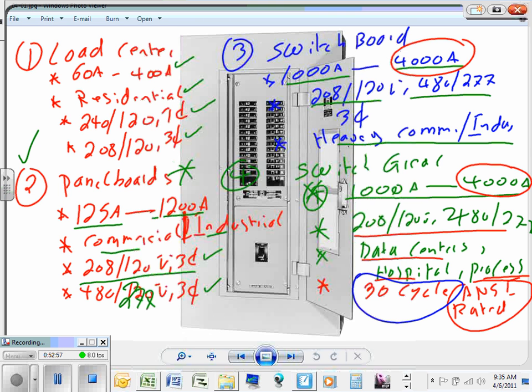Except if it's a switchgear. If you look at it, switchgear is rated for 30 cycles. What does that mean? Suppose it's a switchgear, and I have a short circuit on this switchgear. The short circuit can sit there for 30 cycles. What's 30 cycles? 30 divided by 60 is half a second. I can allow the short circuit to sit here for half a second. That's eternity in short circuit language. So half a second before this circuit breaker trips.